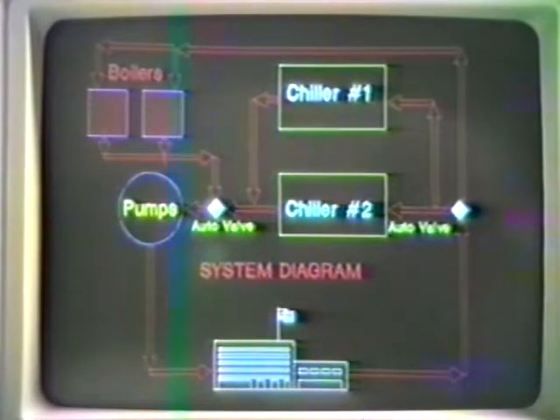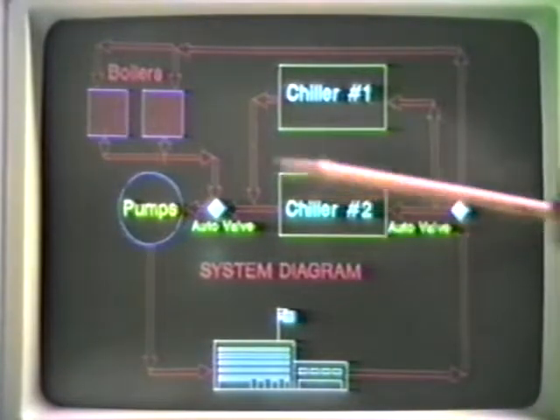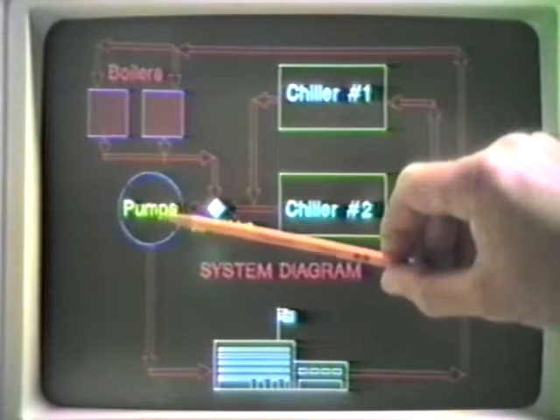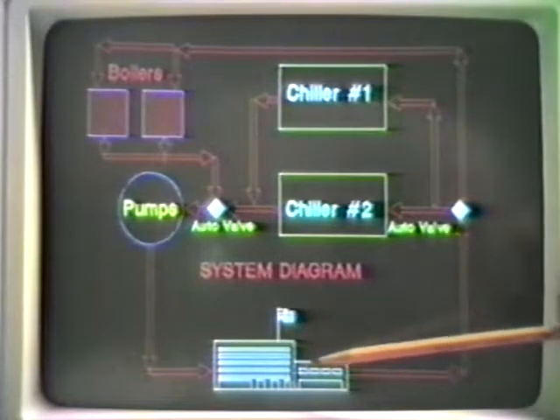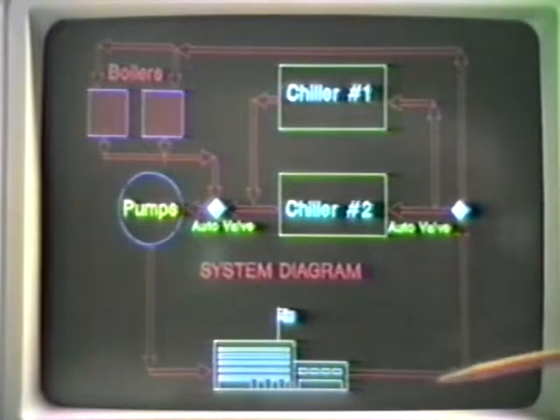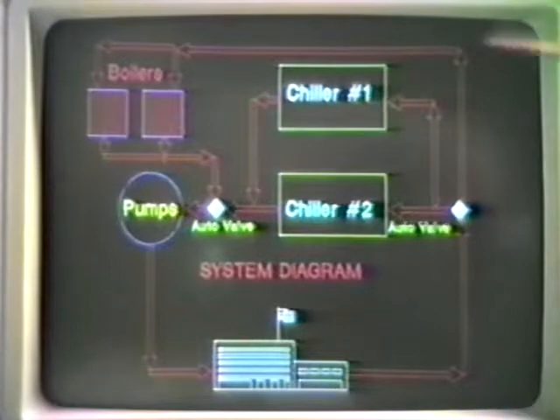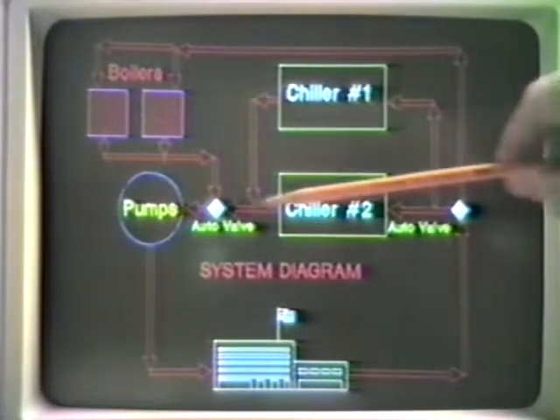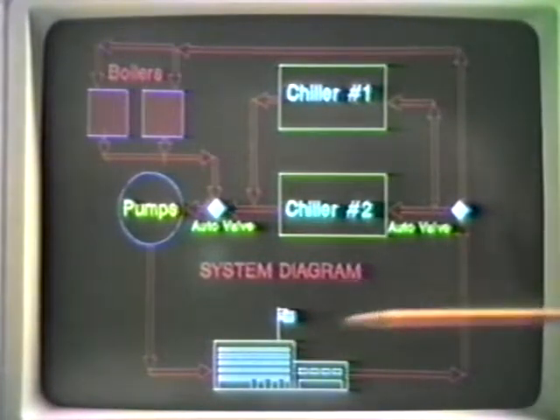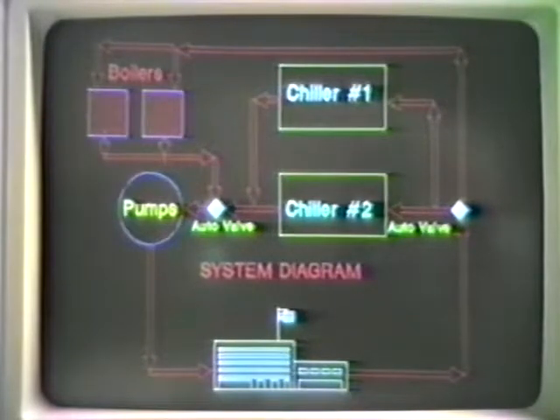We have installed a two-pipe chilled hot water central plant system, the two pipes being one supply, one return line. We pump hot water from the boilers through the pumps into the buildings for the wintertime operation. In the summertime, of course, it's from the chillers through the pumps and into the buildings. The heating and cooling media is a 50% mixture of water and ethylene glycol.